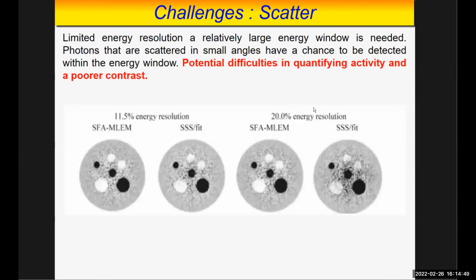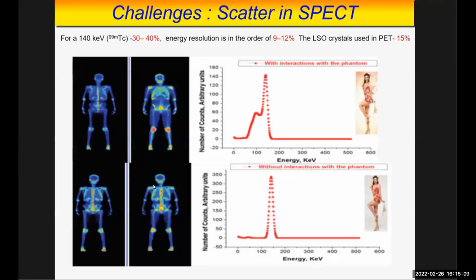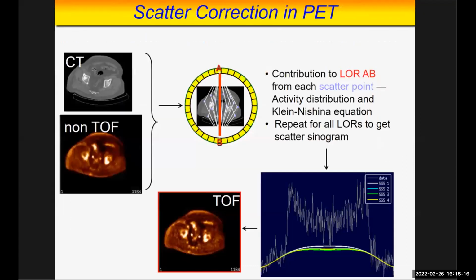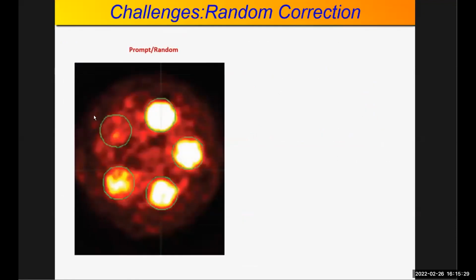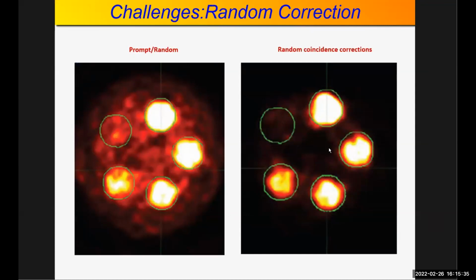You can see here that energy resolution also affects your image quality. When the energy resolution was 20%, the image shows noise, compared to 11.5% energy resolution. This is the second example, where after applying scatter correction the image resolution becomes good compared to without correction. This is the third example, where after applying attenuation correction the contrast resolution increases in the case of a PET image. Random correction also affects your image quality. You can see the image without random correction showing noise, which disappears after applying the random correction.